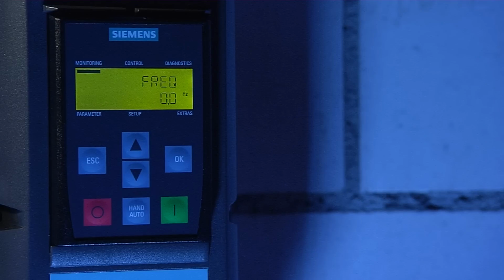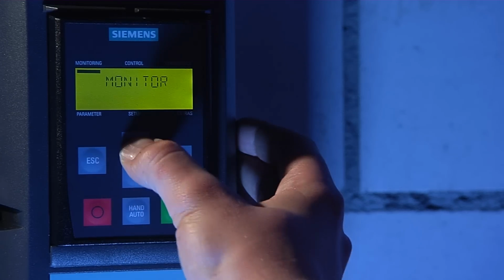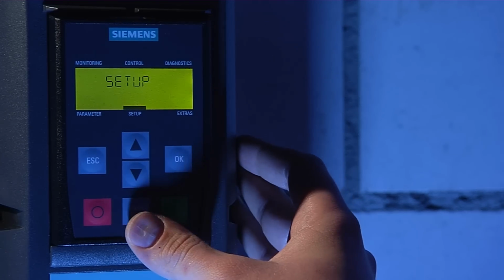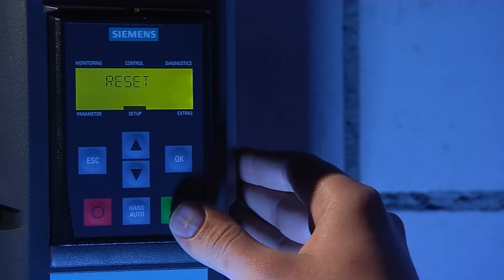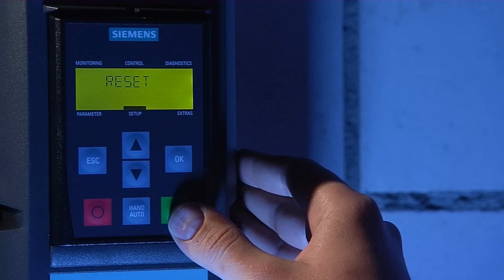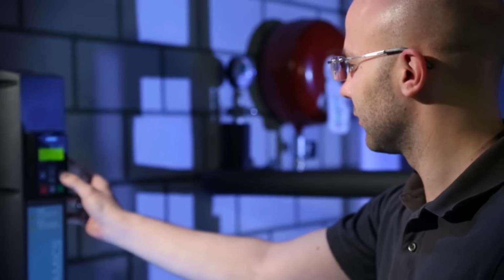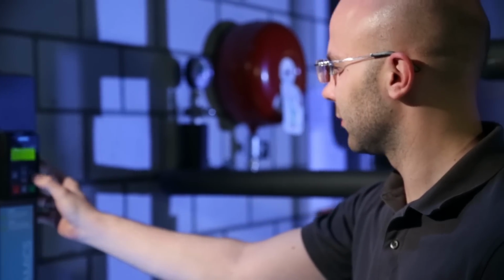To start commissioning, first press the Escape button. The monitor option will start blinking on the display. Press the Up button twice until you see Setup on the display. Confirm by pressing OK. In the first step, the BOP-2 asks you if you want to reset the drive to the factory settings.